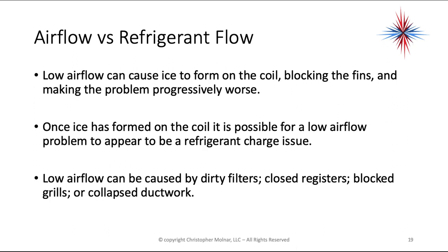Low airflow can cause ice to form on the coil, blocking the fins and making the problem progressively worse. Once ice has formed, low airflow problems can appear to be a refrigerant charge issue rather than an airflow issue. This is why we suggest you always start your diagnosis with the air handler — make sure it is functioning correctly with proper airflow before moving on to refrigeration. Low airflow can be caused by dirty filters, closed registers, blocked grilles, or collapsed ductwork.